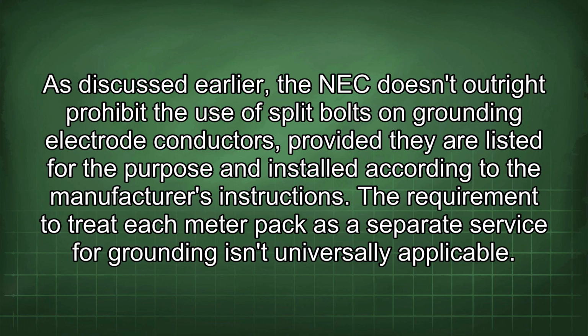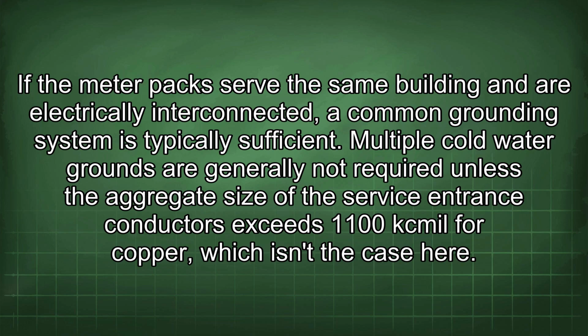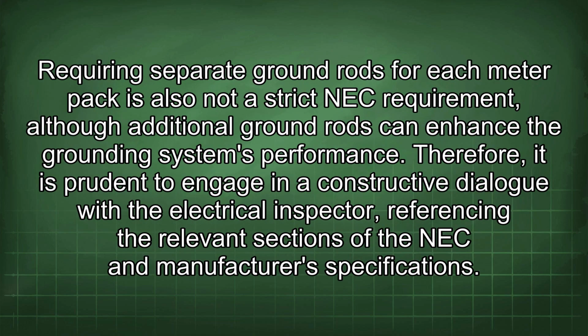The requirement to treat each meter pack as a separate service for grounding isn't universally applicable. If the meter packs serve the same building and are electrically interconnected, a common grounding system is typically sufficient. Multiple cold water grounds are generally not required unless the aggregate size of the service entrance conductors exceeds 1100 kcmil for copper, which isn't the case here. Requiring separate ground rods for each meter pack is also not a strict NEC requirement, although additional ground rods can enhance the grounding system's performance.